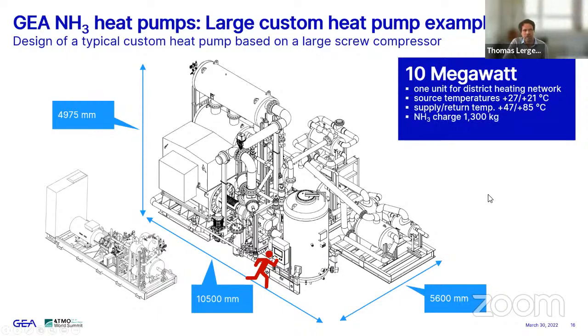Ammonia charge, I said, we are using really little quantities, which is true for most of the standard units that consume between 30 kilogram up to maybe 90, 95 kilogram. Here we have more than 10 times the amount in there for 10 megawatts. This, of course, is a different story, and also the weight is nearly 10 times as much as some of these standard units. So these are totally different dimensions, obviously, but it shows very nicely the range of different solutions and heat pumps that we have.